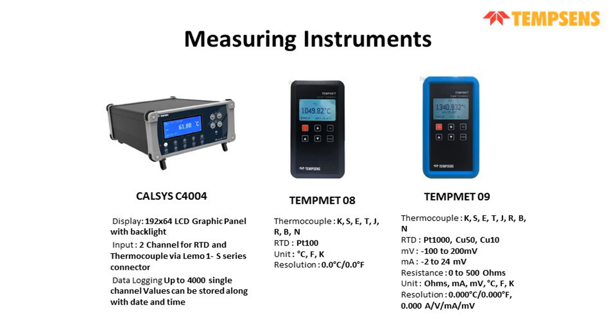These are the types of thermocouples that can be used as an input for this TempMet. And then we have RTD PT1000, CU 50 and CU10. Then we have millivolt and milliamperes that can range from minus 100 to 200 millivolts and minus 2 to 24 milliamperes. Resistance is 0 to 500 ohms, and the units we can change as per our requirements.